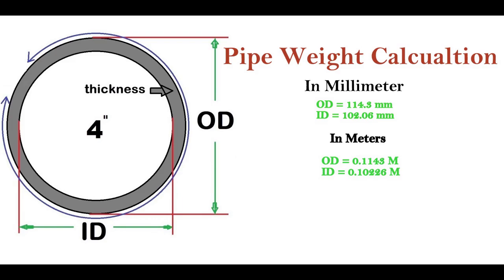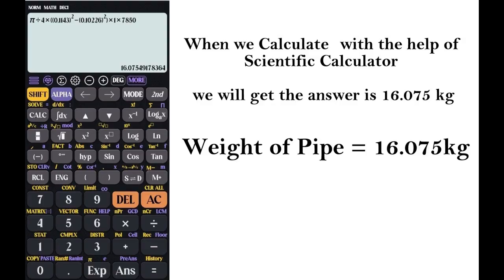So when we calculate with the help of a scientific calculator, after inserting the values of OD, ID, and pipe length, we will get the answer as you see in the image: 16.075 kg. The weight of 1 meter 4 inch pipe is 16.075 kg.